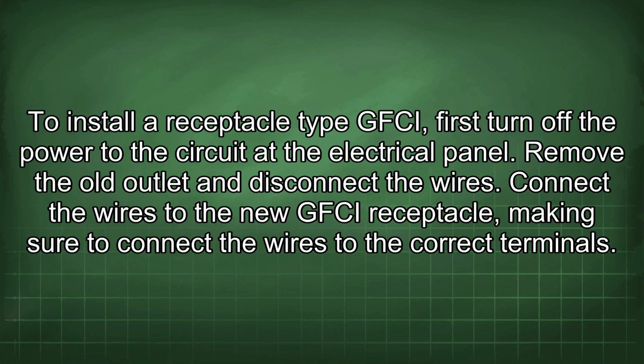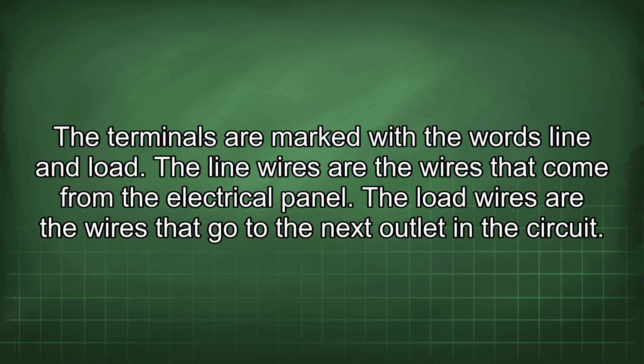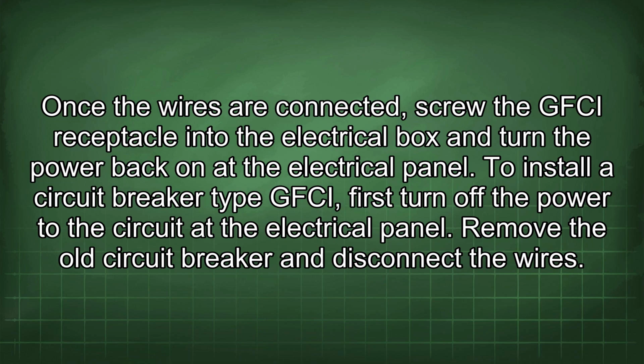To install a receptacle type GFCI, first turn off the power to the circuit at the electrical panel. Remove the old outlet and disconnect the wires. Connect the wires to the new GFCI receptacle, making sure to connect the wires to the correct terminals. The terminals are marked with the words line and load. The line wires are the wires that come from the electrical panel. The load wires are the wires that go to the next outlet in the circuit. Once the wires are connected, screw the GFCI receptacle into the electrical box and turn the power back on at the electrical panel.